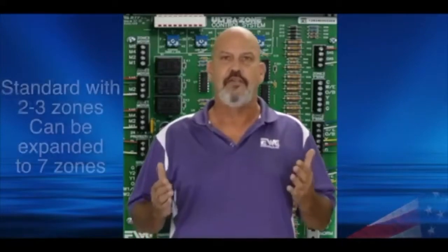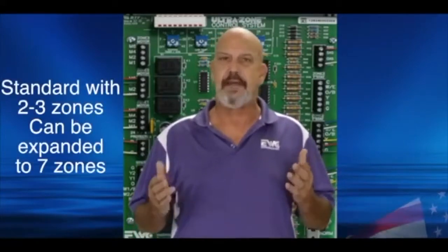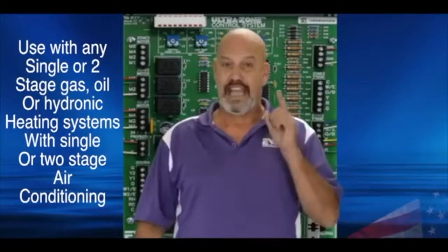Its flexibility and major design parameters are what makes the BMPlus one of the most resilient, comprehensive, and trusted boards in the industry. It comes standard with 3 zones for 2 and 3 zone applications and can be expanded to 7 zones. The BMPlus 3000 can be used with any 2 and 3 stage conventional or dual fuel heat pump systems without the need for dual fuel kits. Also, any single stage or 2 stage gas, oil, or hydronic heating systems with single or 2 stage air conditioning.